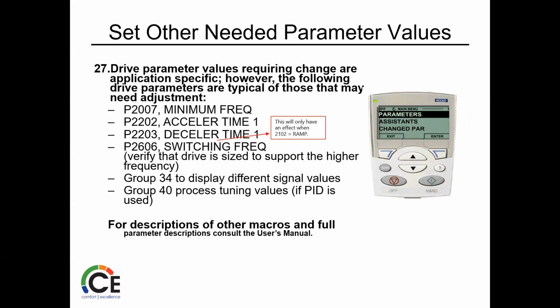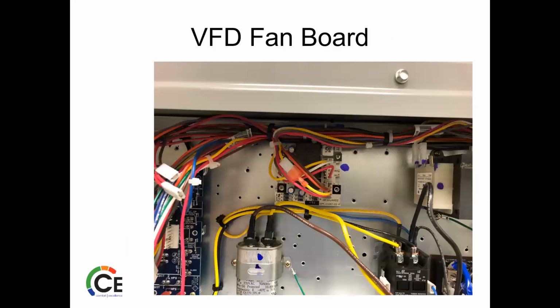Drive parameters. The values requiring change are application specific. However, the following parameters are typical of those that may need adjustment: minimum frequencies, acceleration time, deceleration time, switching frequency. And if you're getting this from the factory, all of this is done. This only comes into play when we're replacing one. Now, at times we get some from the factory that are just whatever. I guess they fell asleep that day. So we still want to double check some things and make sure it's working. I'm going to skip through that because we have more.